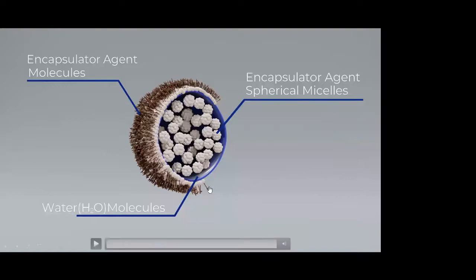A couple of points I want to make: because we've been in the foam business, we understand clearly that the quality and quantity of the foam is really based on the equipment. You're taking an agent, aspirating it with air, and creating bubbles. If we go to UL 162 on the Underwriters Labs website, we see that if a foam is UL listed, it's not really the agent that's listed—it's the agent listed with a foam nozzle and a foam eductor. It's important to understand that, because when you put that product through a different device, it actually changes the performance of the foam.